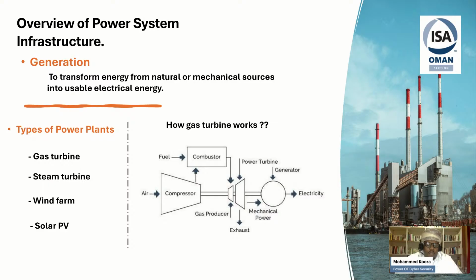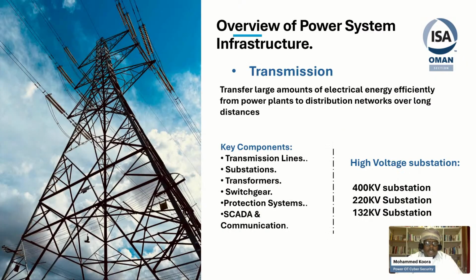But unfortunately, the utility—residential or industrial—will never be near our generation plant. So we need to transfer this power to the distribution system through another section, which we call the transmission section. What's the aim of the transmission section? It transmits our electrical power from the generation power plant up to distribution. The main concept is that we try as much as possible to raise the voltage level to reduce power losses. So in transmission, you will always find voltage levels more than 132 kV, 220 kV, and above.